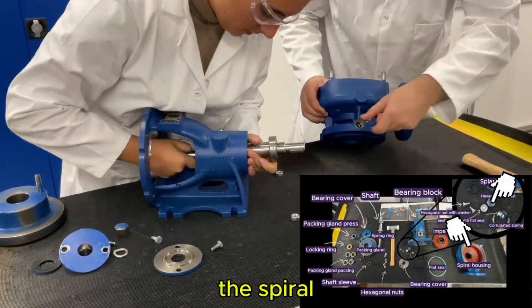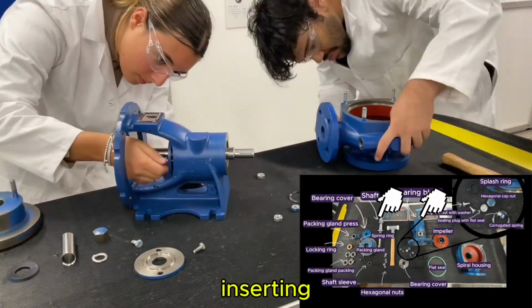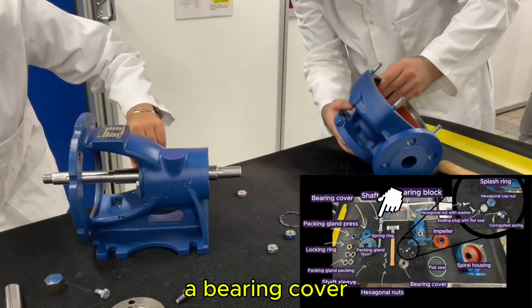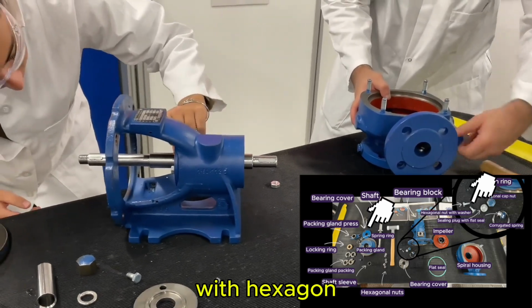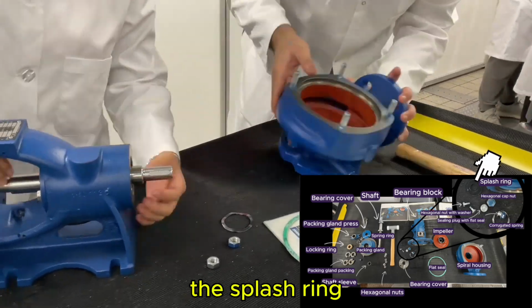We start by securing the spiral housing with sealing plugs with flat seal while simultaneously inserting the shaft to the shaft bearing block. We then secure a bearing cover at the inner side of the bearing block and secure it with hexagon head screws. Follow it by placing the splash ring in the middle of the shaft.